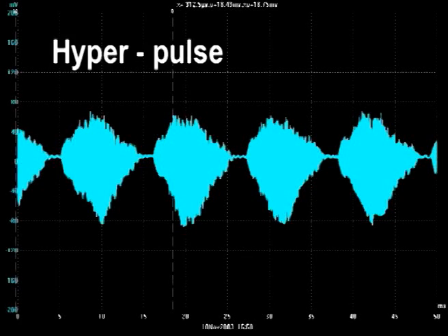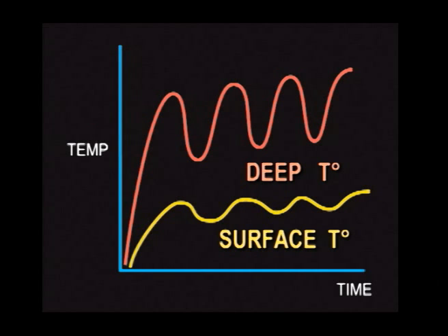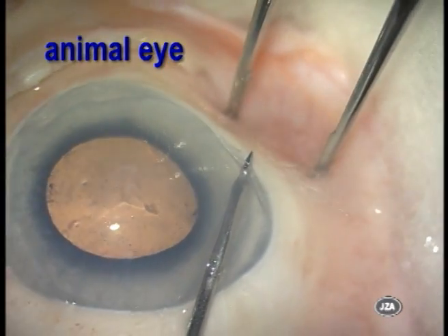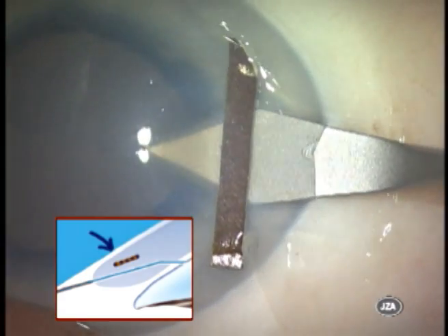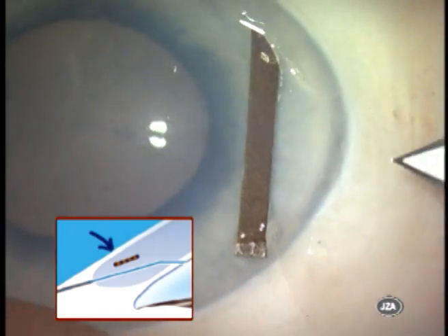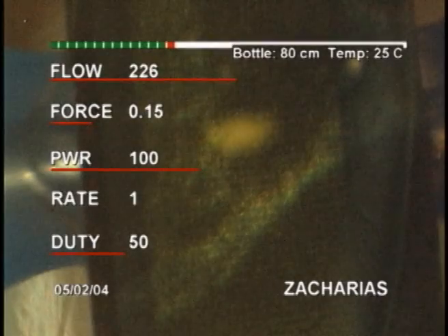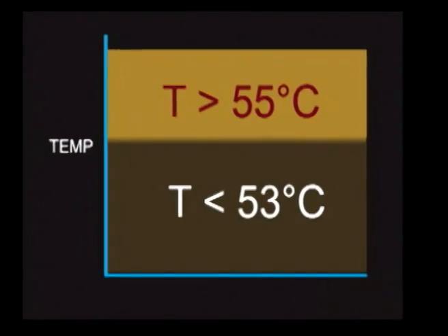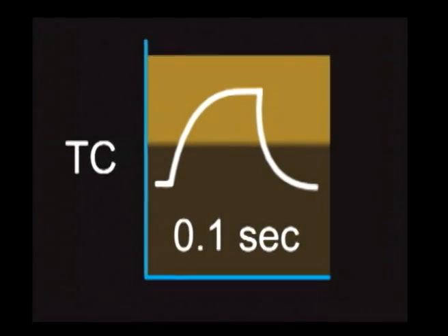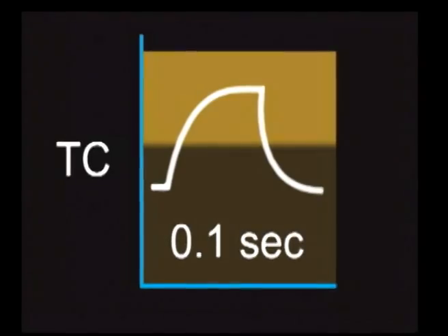To determine if hyperpulses really produce less heat than standard pulses at the incision site, we devised a new technique to obtain fast-responding, in-depth temperature measurements. Our novel method considers the implantation of a thin, temperature-sensitive film midway between the incision roof and the corneal surface. This film will totally shift color from dark brown to yellow when temperature rises from 53 to 55 degrees centigrade, acting as a threshold temperature sensor. The time constant of the sensor film to change color was below 0.1 second.